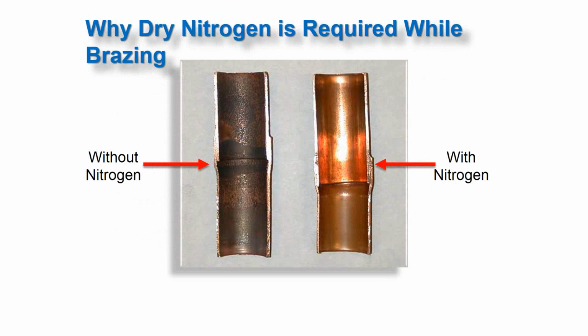This is just a picture of what it would look like if you did not purge your lines with nitrogen while brazing. All this sediment is oxidation from the flame, from the torch, from brazing. When you purge with nitrogen, this is what the inside of the pipe looks like. Doesn't look like there was ever a torch on there.